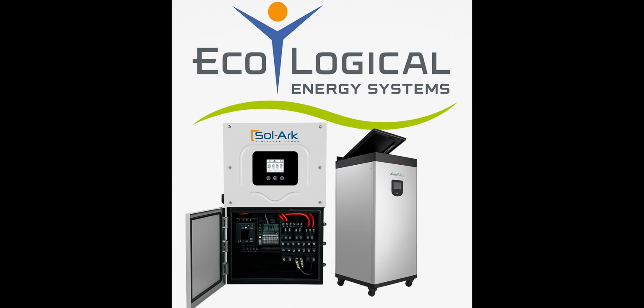Where's the best place to put this battery? Are there any specific environmental conditions it needs? It's designed for indoor installation in a location that's protected from water and has a flat, level floor to support its weight. Indoors, dry, level. Keep it away from anything flammable or explosive. The ideal operating temperature range is between 59 degrees and 95 degrees Fahrenheit. That's operating, different from the warranty survival range. All right, ideal operating, with stable temperature and humidity and as little dust and dirt as possible. For storing the battery long-term, the recommendation is to charge it to around 60% state of charge. 60% for storage.